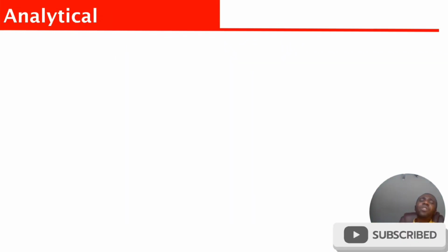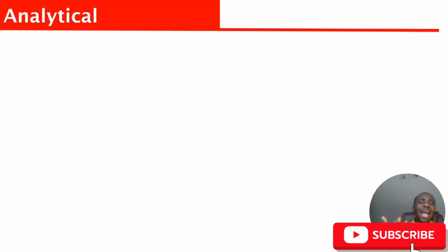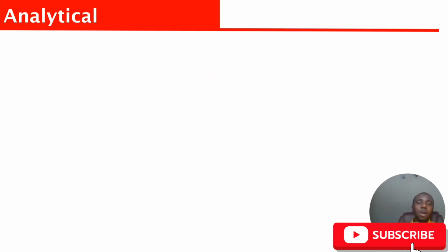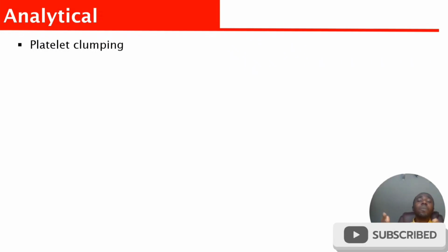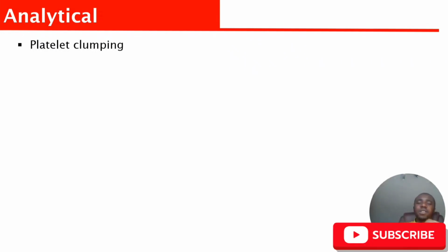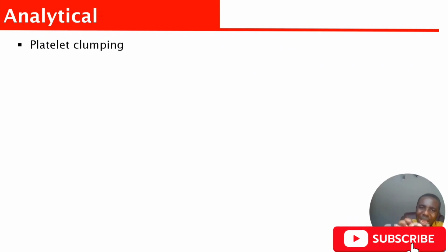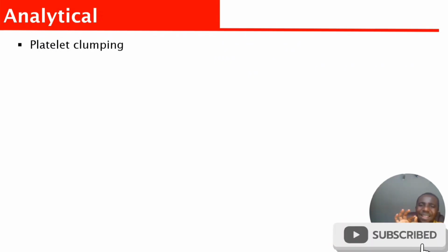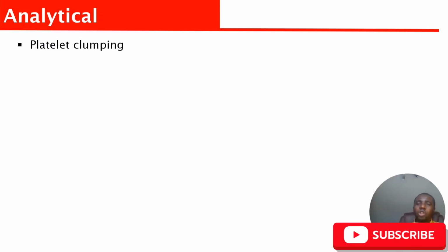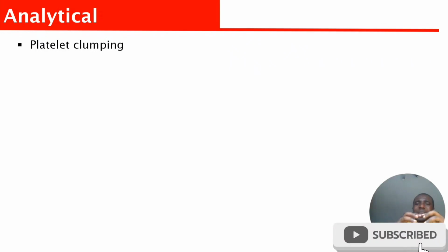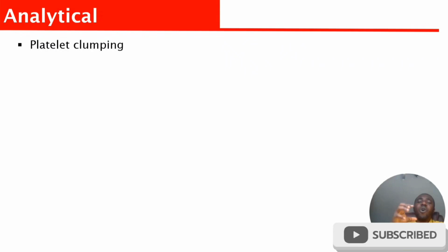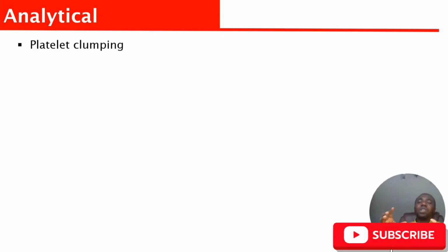Now let us look at the analytical phase. What can lead to low platelet count from the analytical point of view? Number one, it could be due to platelet clumping. This is important, if you remember what I explained previously about platelets passing through the aperture, each of the cells needs to pass through, and as it passes, the analyzer will be counting. But where there's a platelet clump, a bunch of platelets clumping together, that clump will make it difficult for the analyzer to count the actual platelet count.